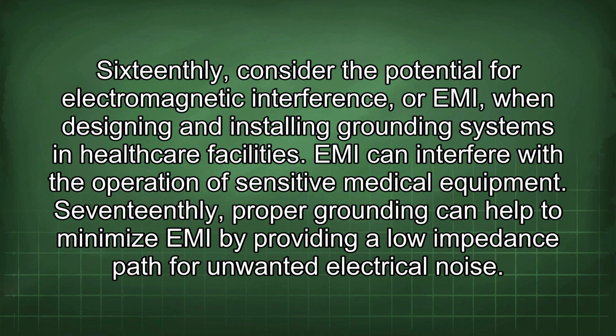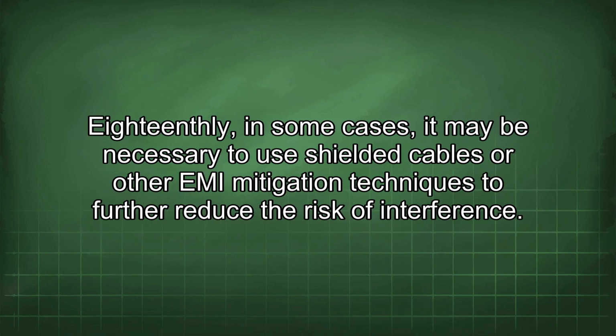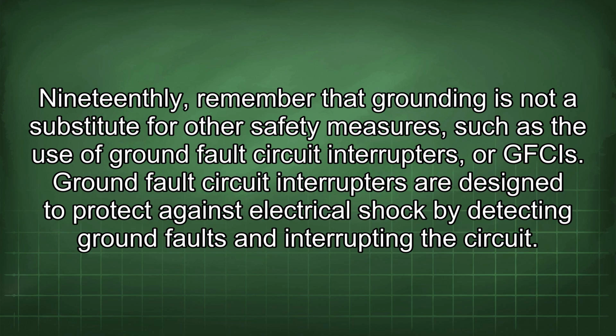Sixteenthly, consider the potential for electromagnetic interference, or EMI, when designing and installing grounding systems in healthcare facilities. EMI can interfere with the operation of sensitive medical equipment. Seventeenthly, proper grounding can help to minimize EMI by providing a low impedance path for unwanted electrical noise. Eighteenthly, in some cases, it may be necessary to use shielded cables or other EMI mitigation techniques to further reduce the risk of interference.